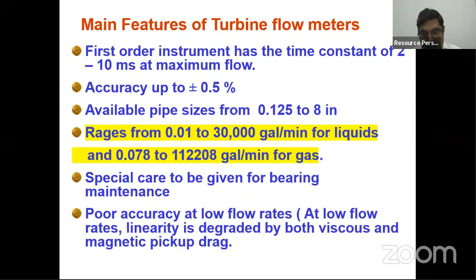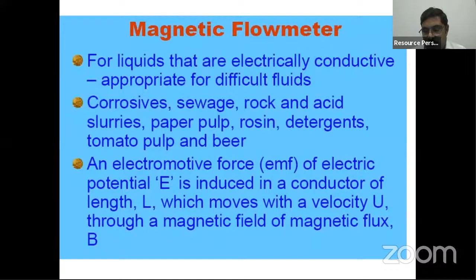And if the diameter is too big, then we have to go for the ultrasonic type flow meter. Basically it's a non-contact type flow meter. Of course, because of the time constraint, I am not covering it, but it's a special type of flow meter available. And suppose the fluid is highly hazardous and you cannot touch it, then we can go for the magnetic type of flow meter. But in the magnetic type flow meter, the fluid should have some minimum conductivity, then only you can use it.